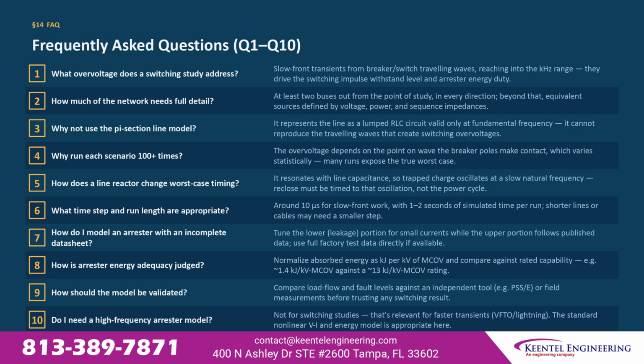Here are answers to 10 common questions about switching overvoltage studies. What type of overvoltage does a switching study address? Slow front transients from breaker and switch operations reaching into the kilohertz range. These events drive the switching impulse withstand level and surge arrestor energy duty.